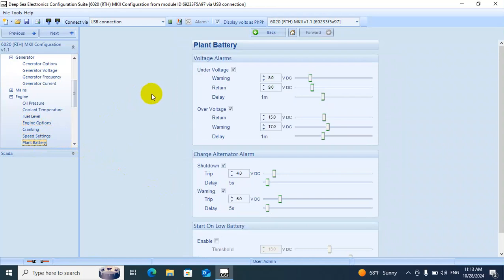This option is just for 12 volt DC, if we are using one battery. Under voltage alarm, return, and over voltage: when it reaches 15, return, if it reaches 17, it will give a warning. And also the charging alternator alarm: if it reaches 4, the generator will be shut down, and the warning is 6.